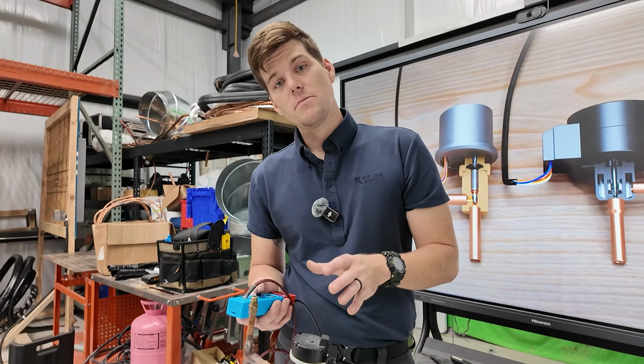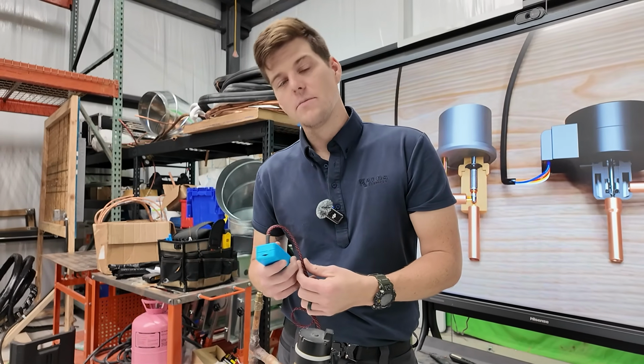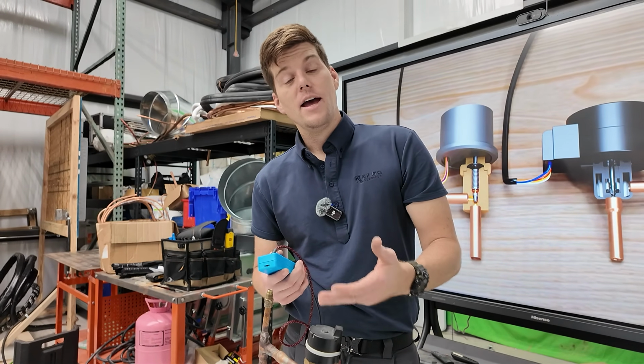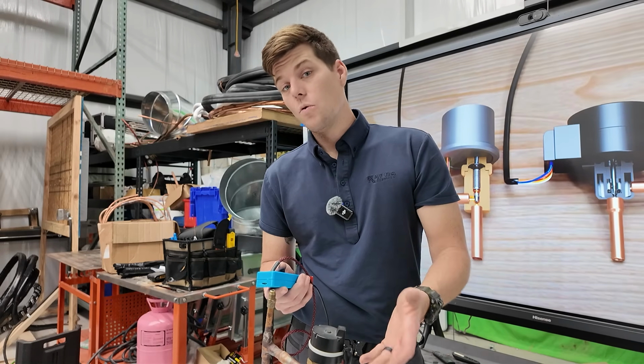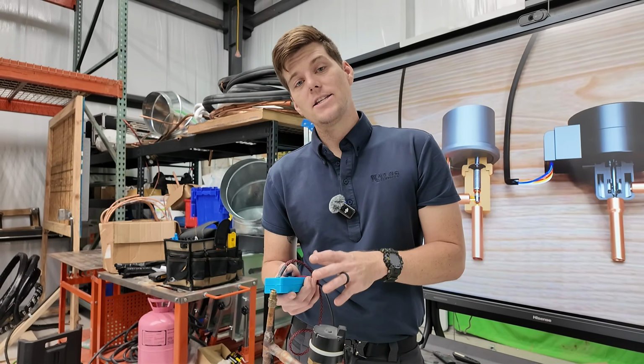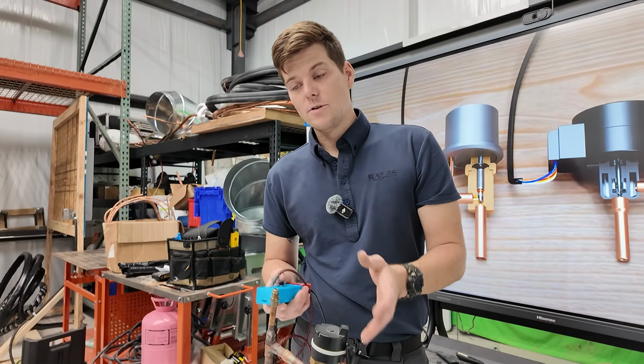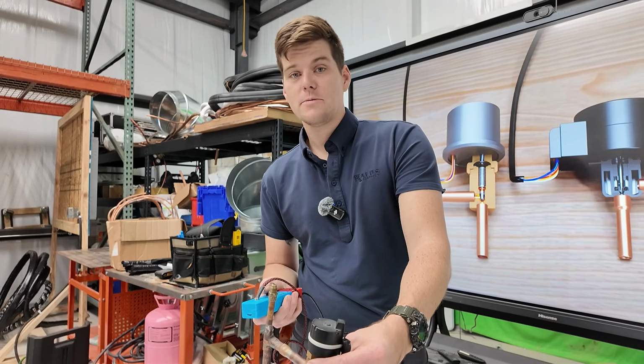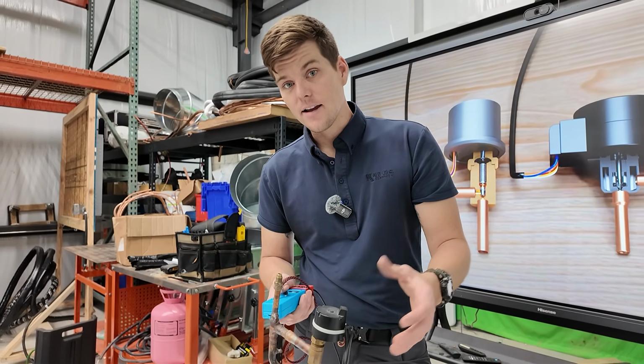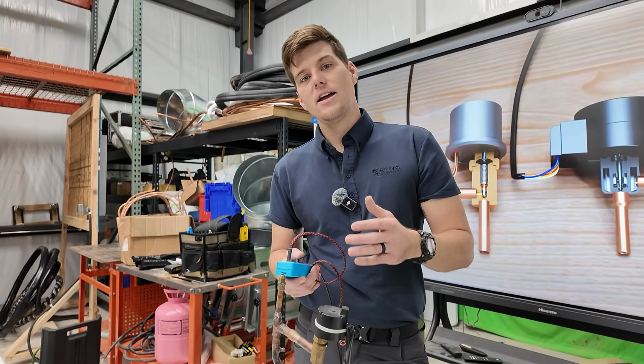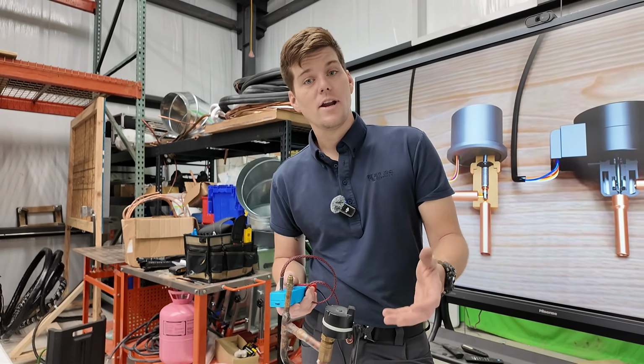And the reason we would need a tool that can do something like that is because if a valve is stuck and not closed all the way, or a valve is stuck and won't open up, we can force it open and possibly get it unstuck. Now, I would still recommend that you replace the internal components of that expansion valve if it is stuck or sticking, but this tool allows you to test that and kind of pull something out of your toolbox that you normally wouldn't have access to.